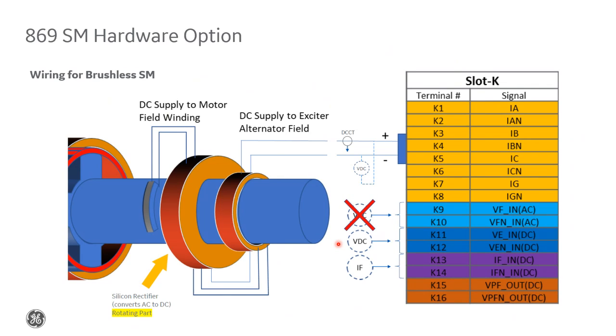Like I mentioned earlier, for brushless applications, the excitation system is fixed and rotating on the shaft. So we have no real way of getting fixed wiring to measure the rotor winding voltage. In this case, we'd leave the signal out, nothing connected here, but we'd still connect the rest as usual. Again, the only implications are on elements that rely on this specific measurement, like the start sequence control, speed option, the speed dependent thermal model, and a couple other options.